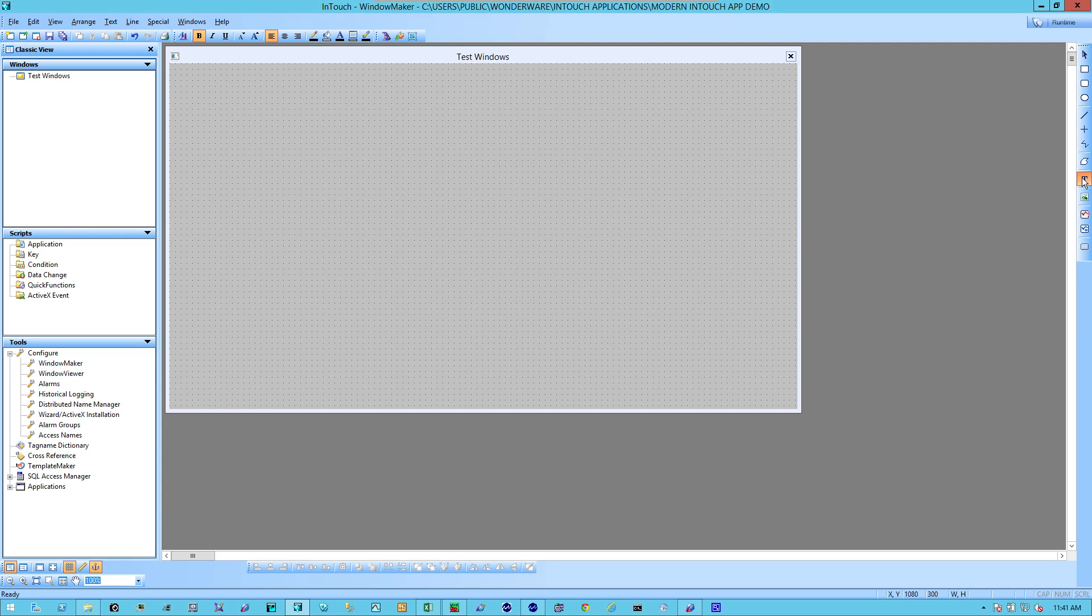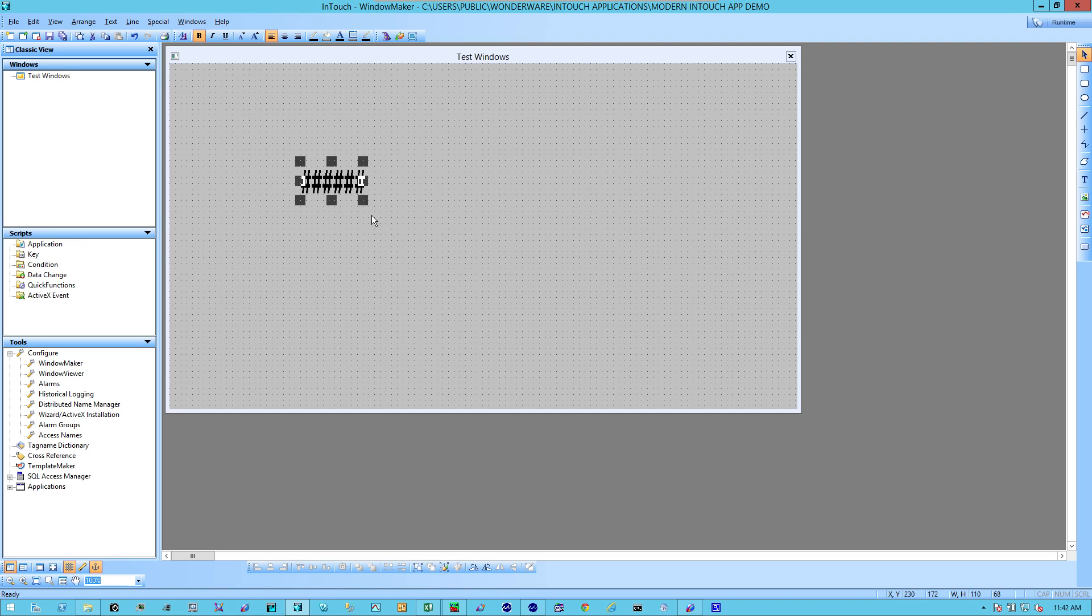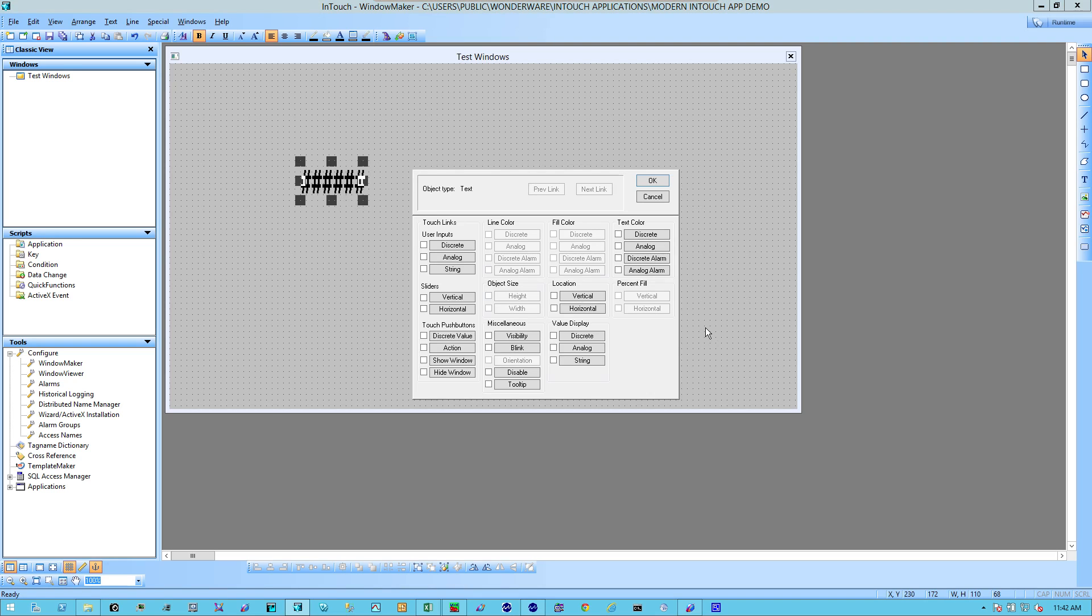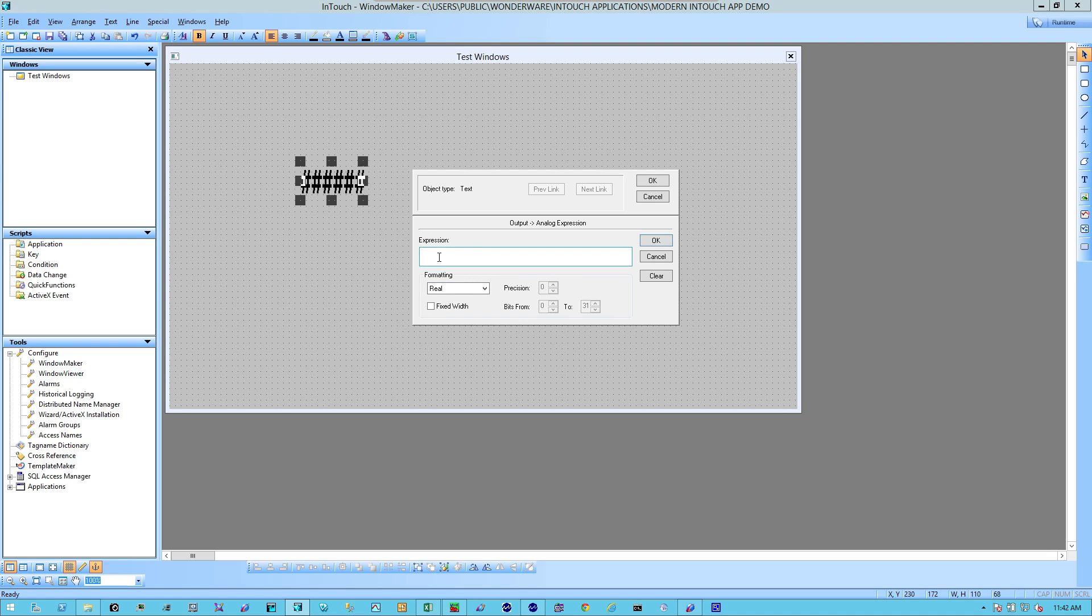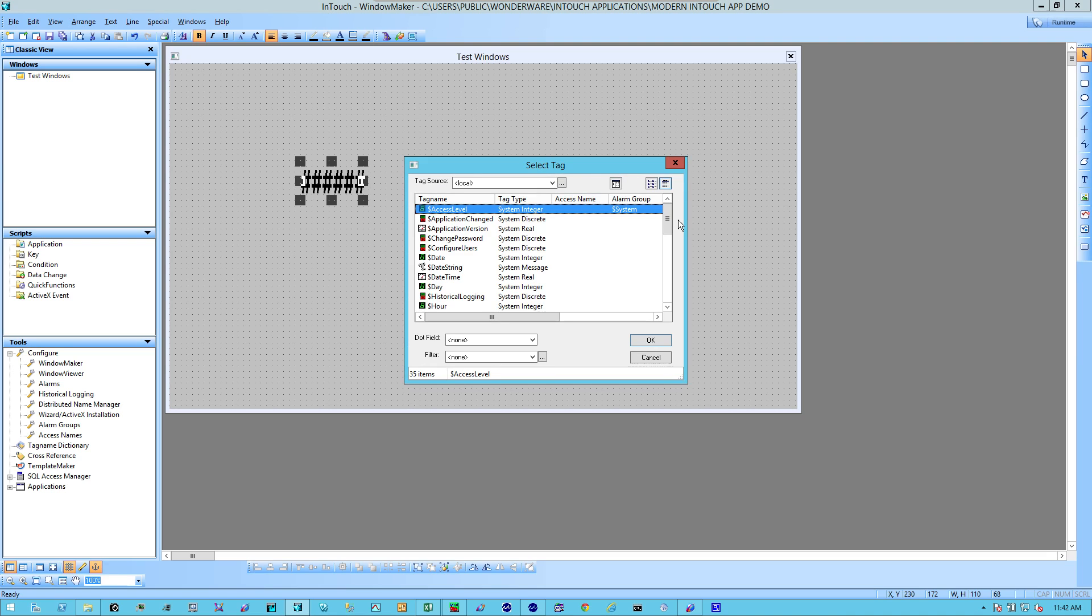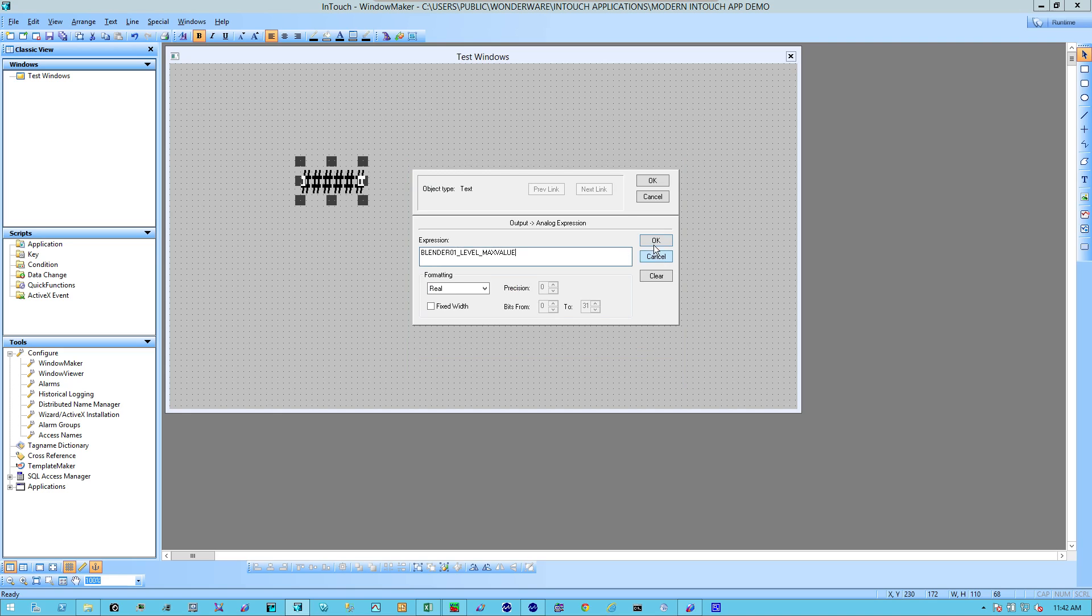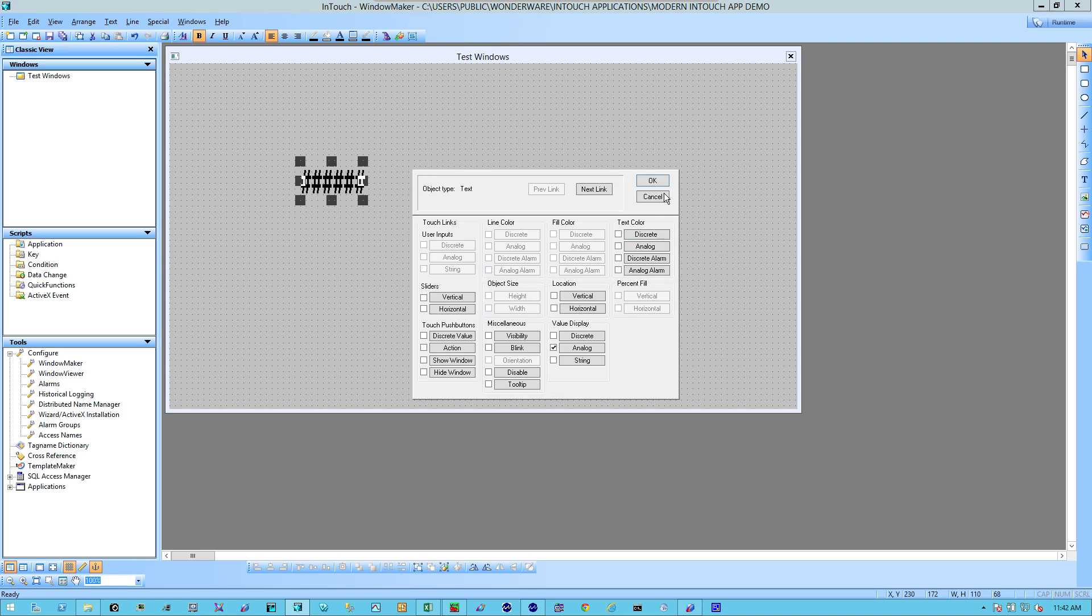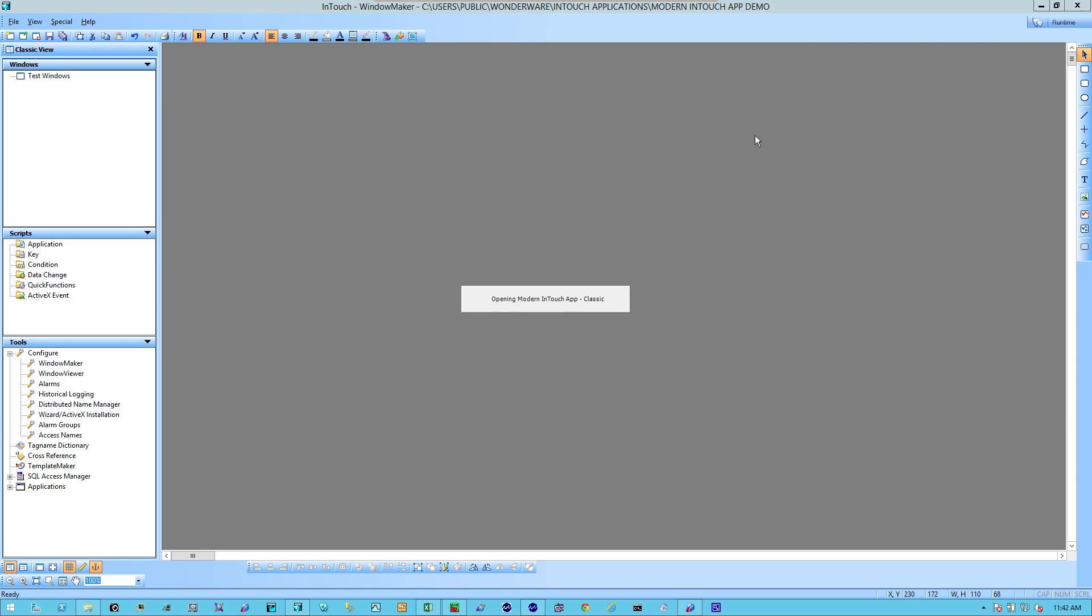Now let's put that value on the screen. I'm just going to put a simple value on the screen, just a bunch of pound symbols. I'm going to tie these symbols, this particular graphic, to a value. So I want to display an analog value. As far as the formatting, it's going to be a real. If I double click in the expression box, it brings up the tag browser. I'm going to select my tag, say OK, and say OK again. OK to close out the animation editor. And I can go to Runtime.